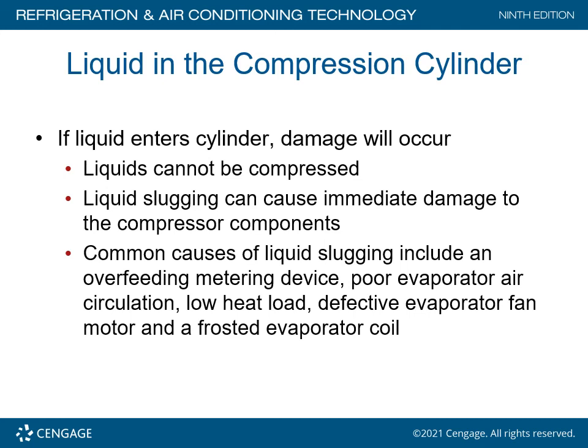Liquid in the compression cylinder will cause damage — liquids cannot be compressed. Liquid slugs can cause immediate damage to compressor components. Common causes of liquid slugging include an overfeeding metering device, poor evaporator air circulation, low heat load, a defective evaporator fan motor, and a frosted evaporator coil.